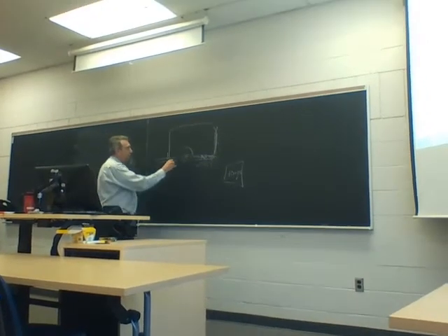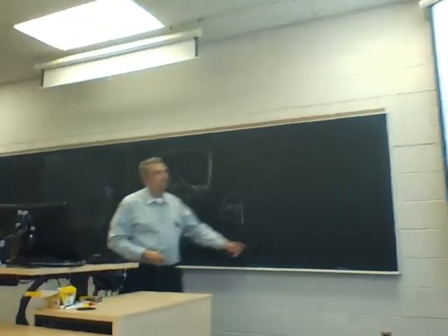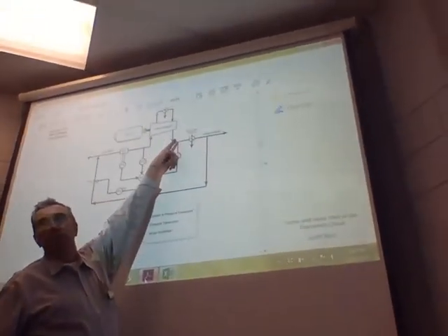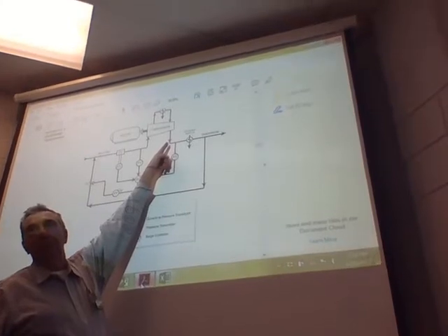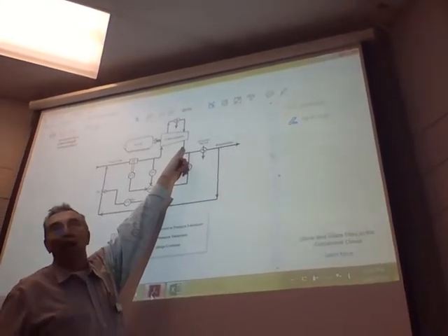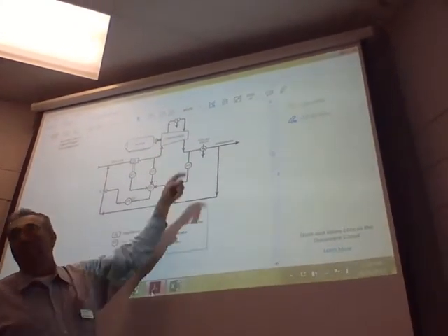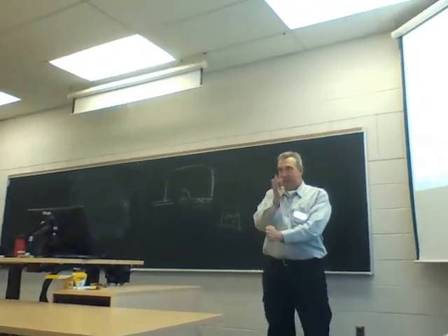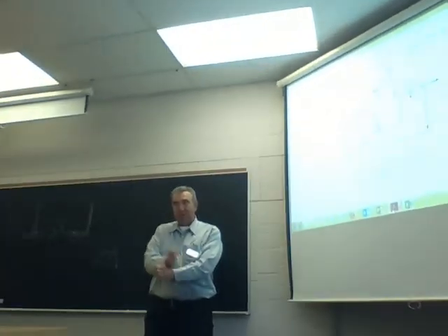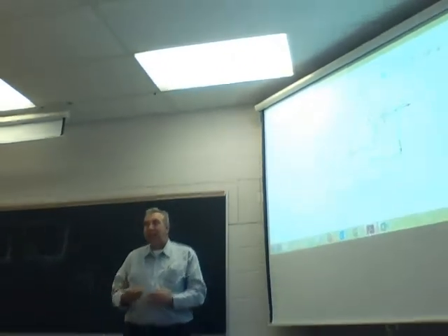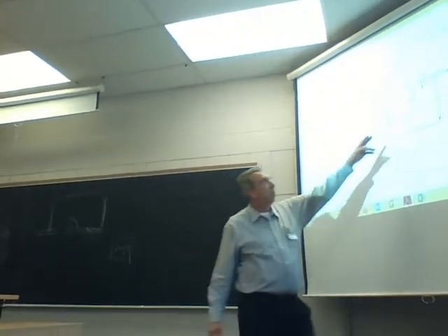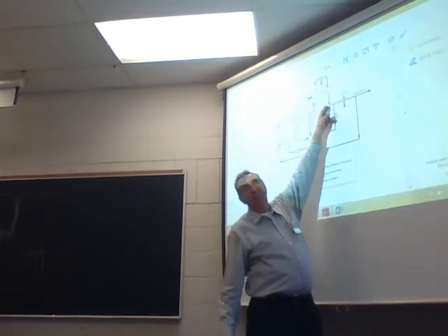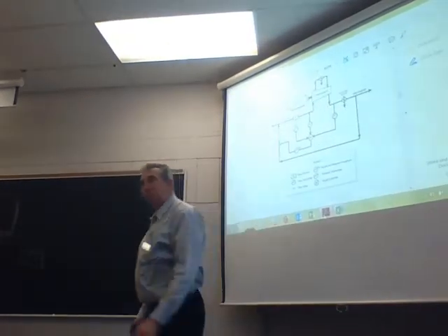What about if this is a 3 or 4 stage compressor? We're using an axial flow here, so we've got pressure in between each one of those. So you're actually going to get surging back from the high end to the low end, right inside the compressor. You see what I mean? From fan blade to fan blade to fan blade, there's going to be differential surging. So that's why the surging will be right in the compressor. The check valve over here would prevent any surging coming back from the receiver, but it won't do anything from inside the compressor itself from stage to stage.